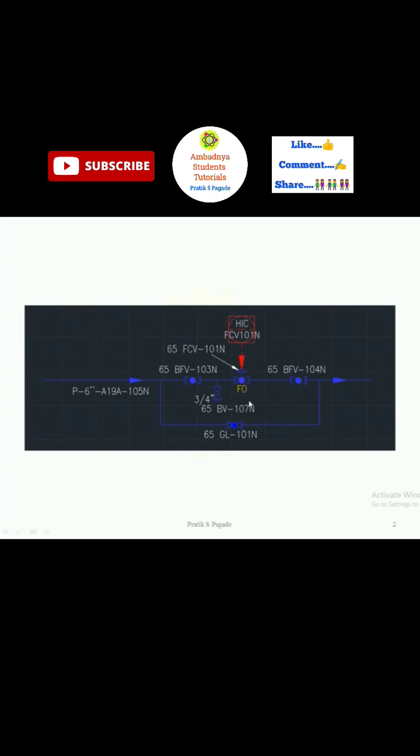This FO indicates fail to open position. That means when signal fails, instrumentation fails, there is any problem, this valve gets fully opened.